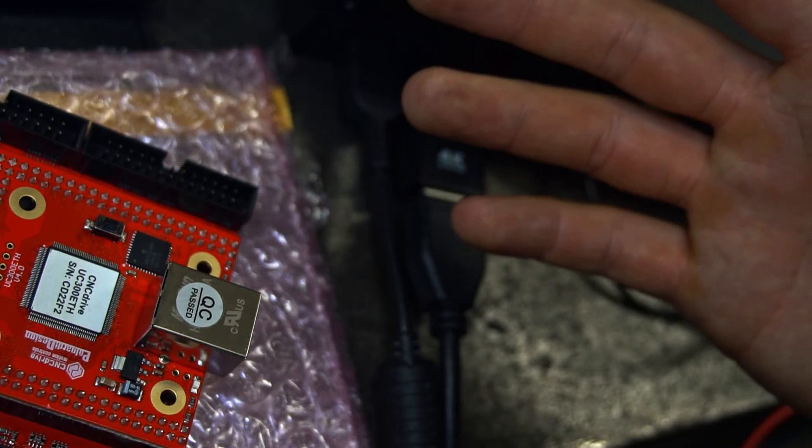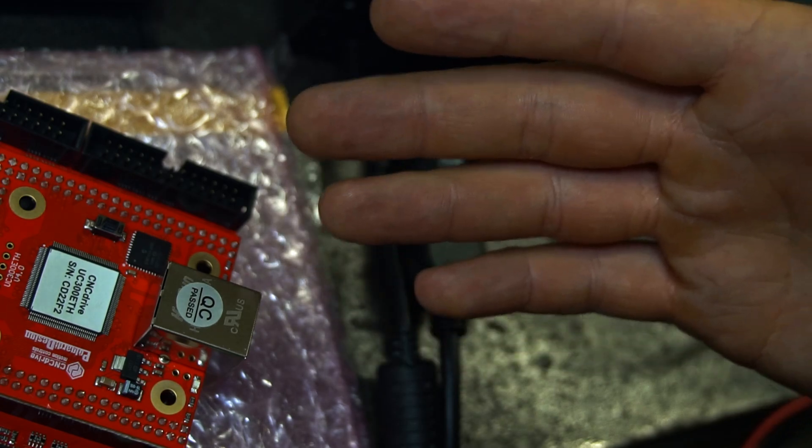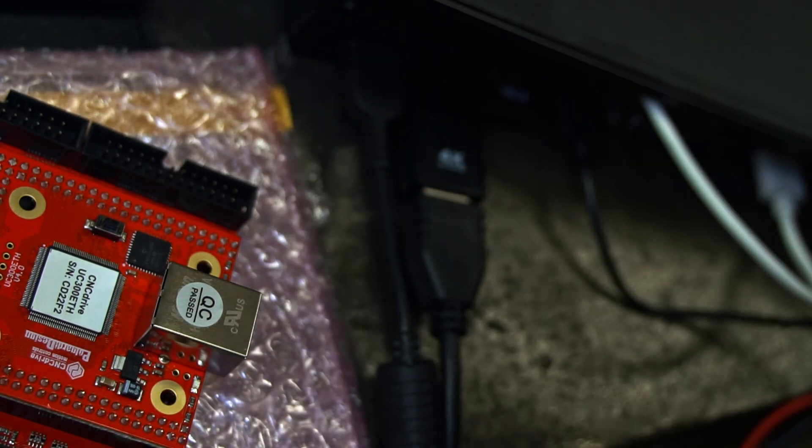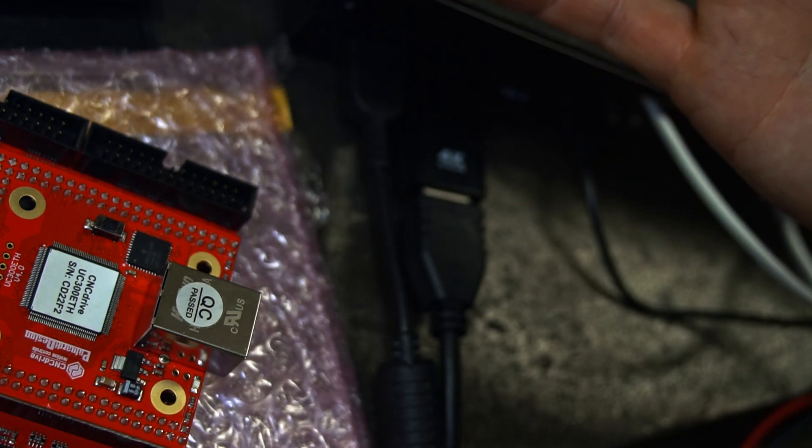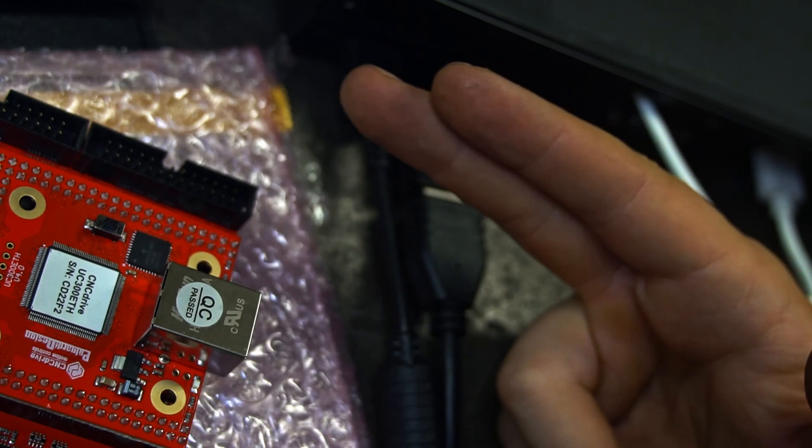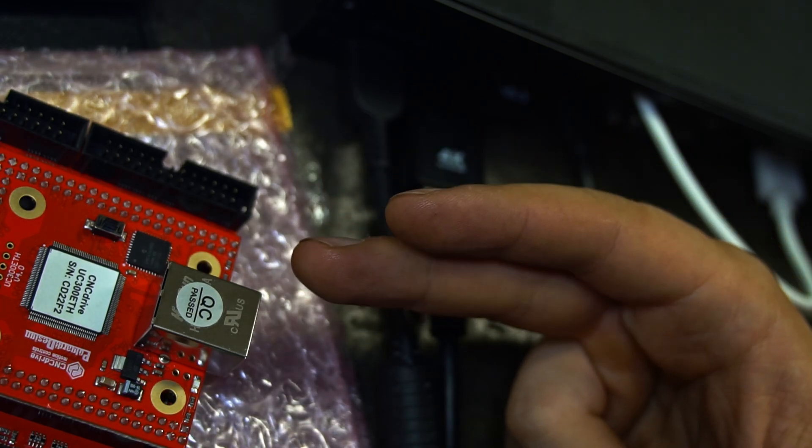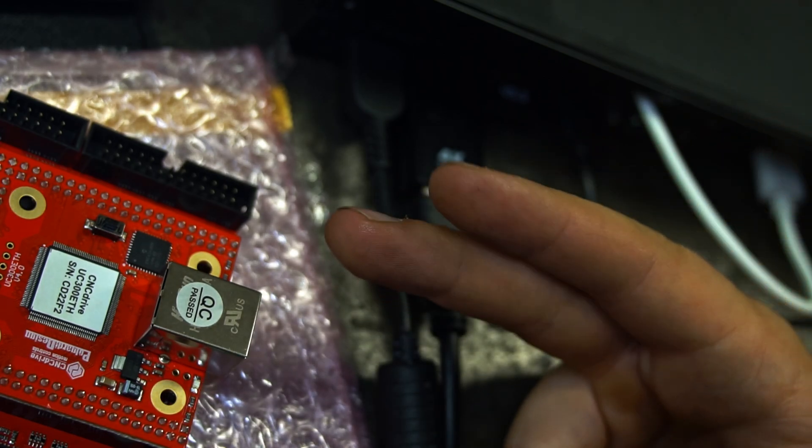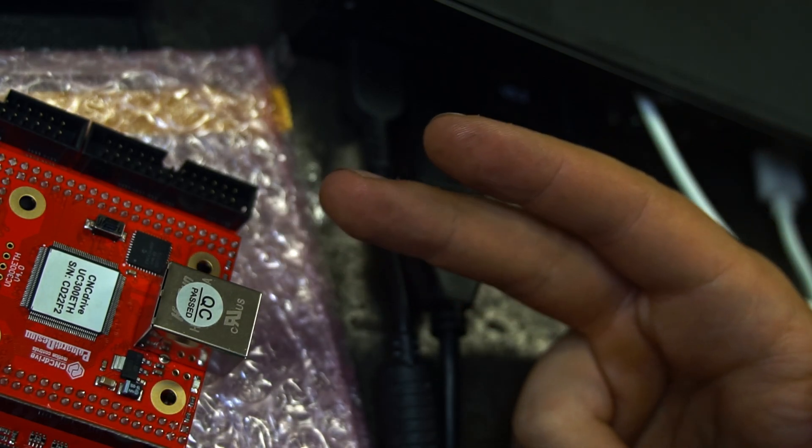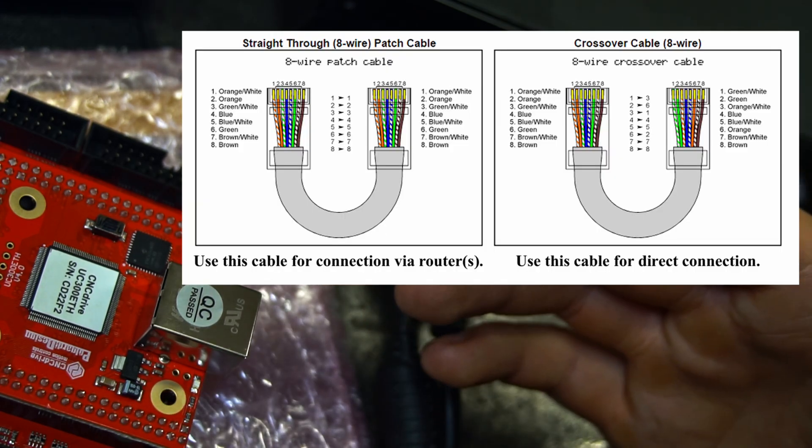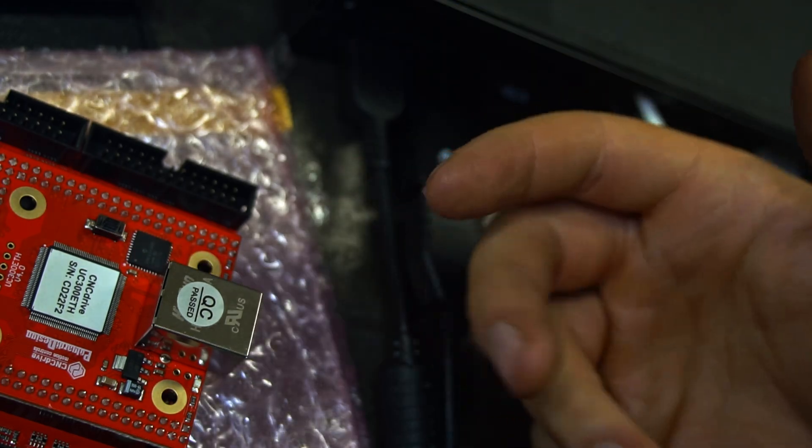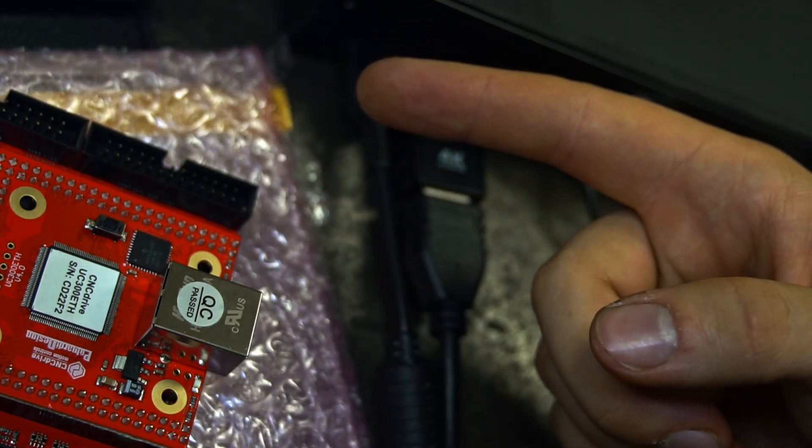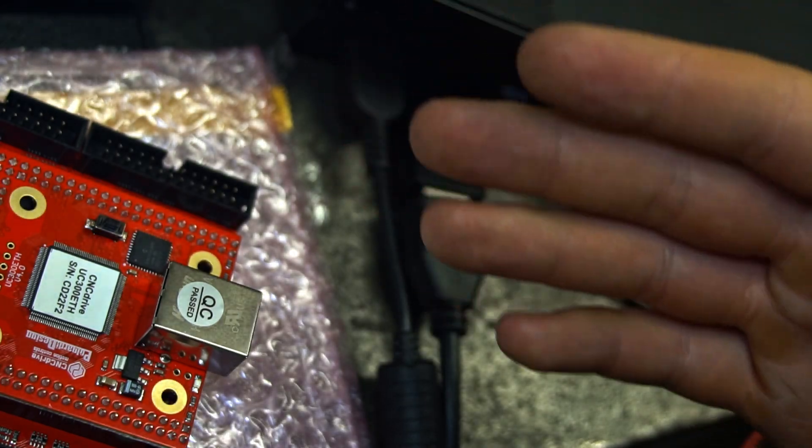Now speaking of the ethernet port. To connect the computer to the port of the controller, we need an ethernet cable. But there are two different types of ethernet cables: straight ones and crossover ones. We can use both of them to connect the controller to the PC. But if we want to use a straight cable, we would have to connect it through a router. And if we want to plug it in directly to the PC, we can use a crossover cable. The difference between the two was described in my video about AXBBE, so if you're interested, check out that video. Link in the description. So speaking of the connection, I will use the crossover cable now to connect it to my computer.